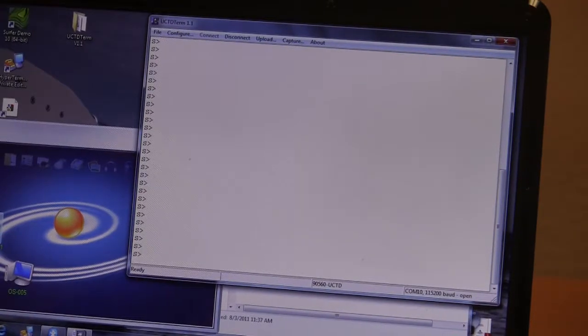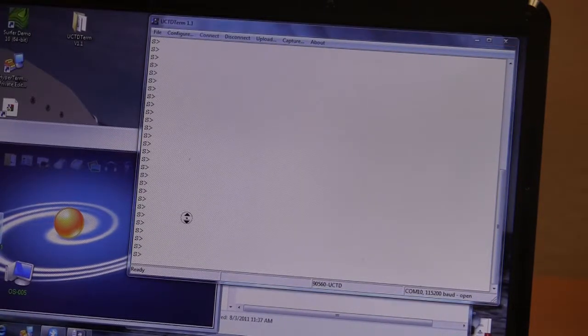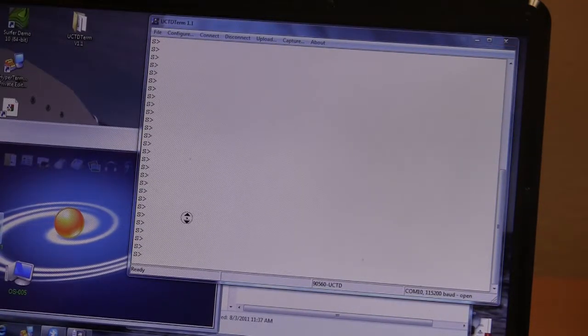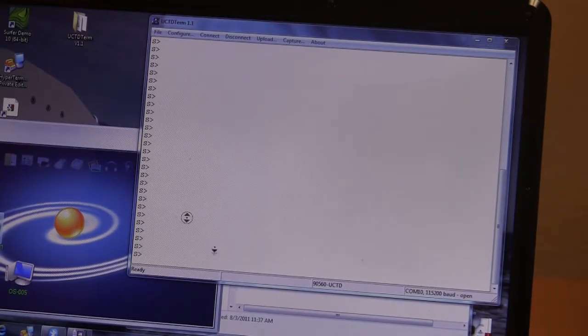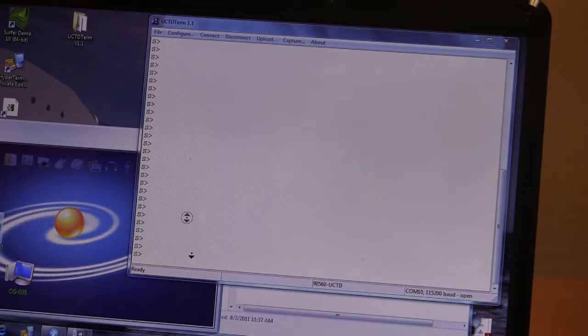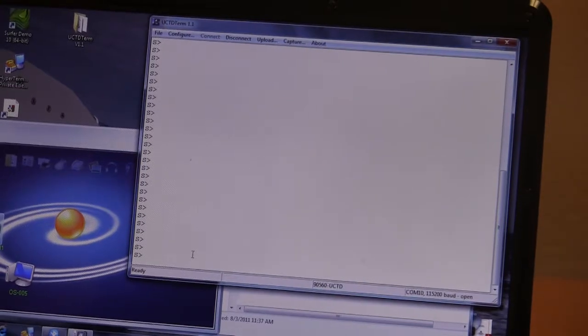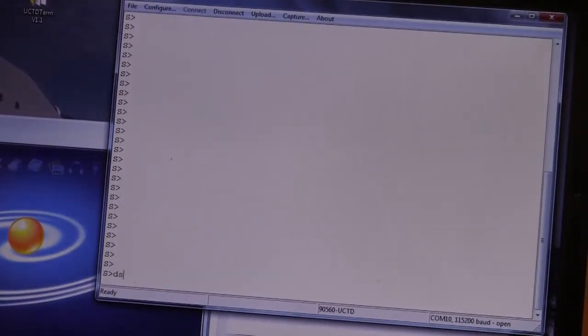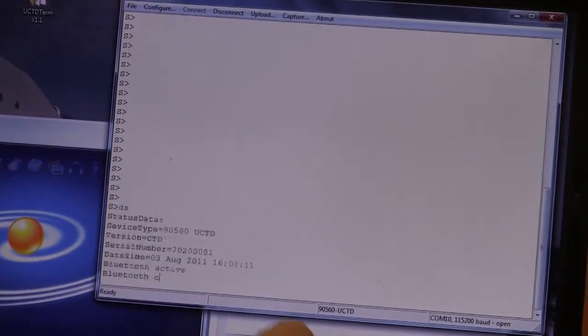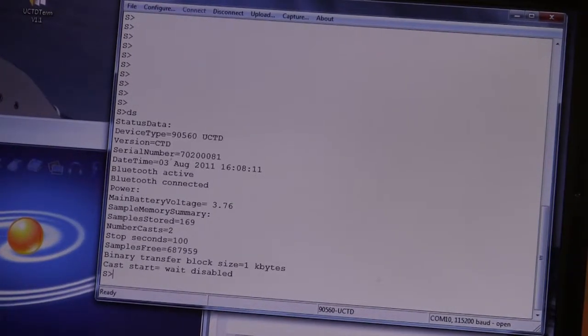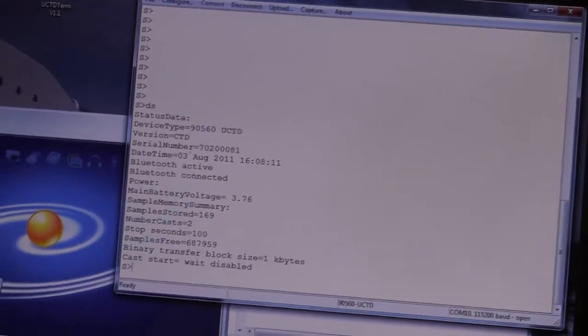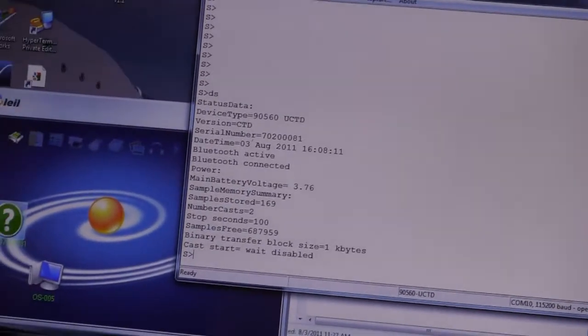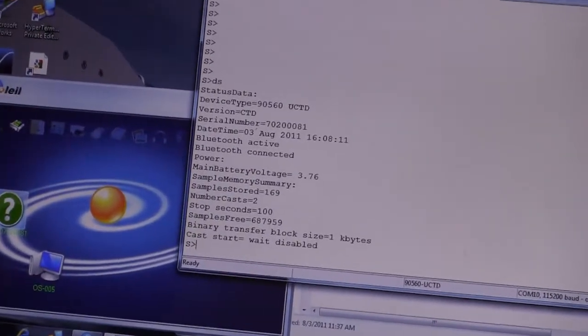Now we're just going to check on the status of the probe. You use the DS command for that. DS, display status. That gives you some vital information about the probe's condition.